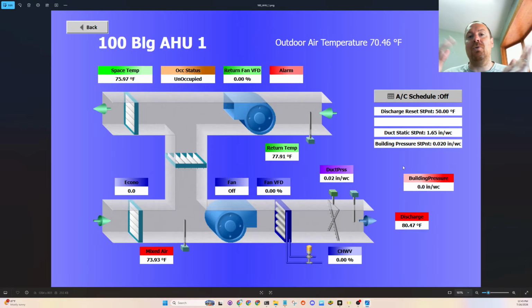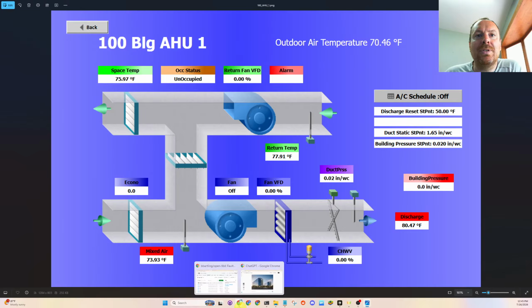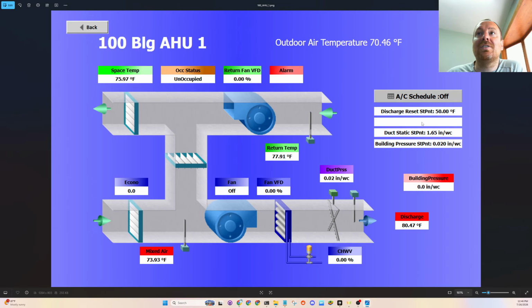And then someone had to lower that down to 50, more than likely because there was probably a very large building full of glass, and there's probably some portion of the building that is not cooling properly. The problem is when these set points are left in place to operate like that year round, probably because it was just peak summertime conditions, then there's a ton of wasted energy in that. Then the ideal thing to do would be during the shoulder season.